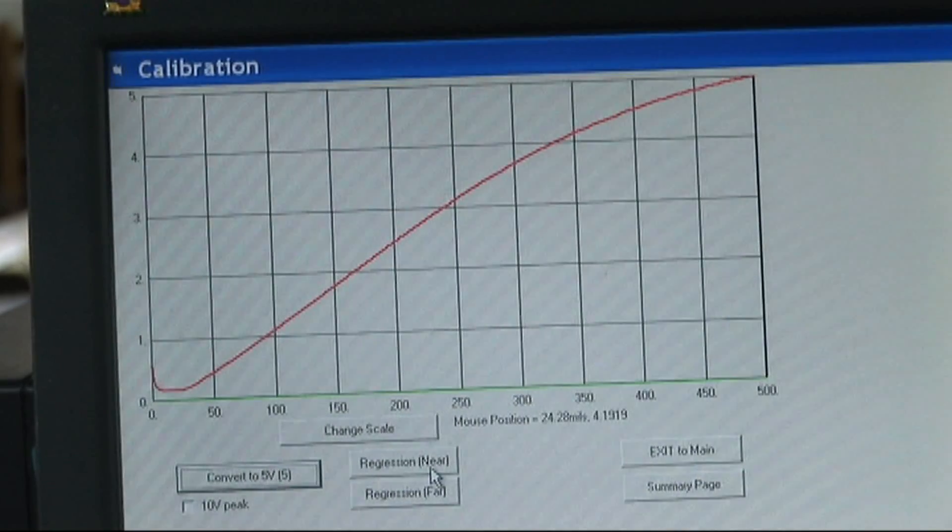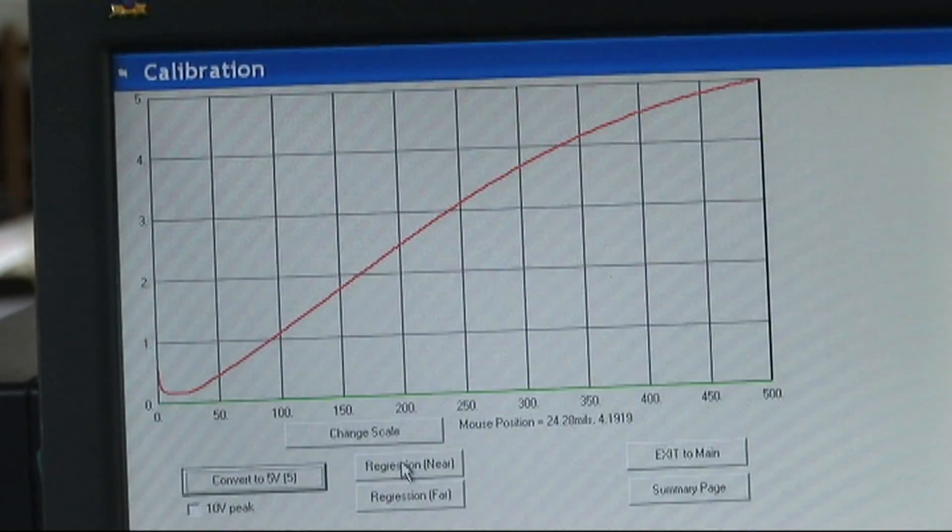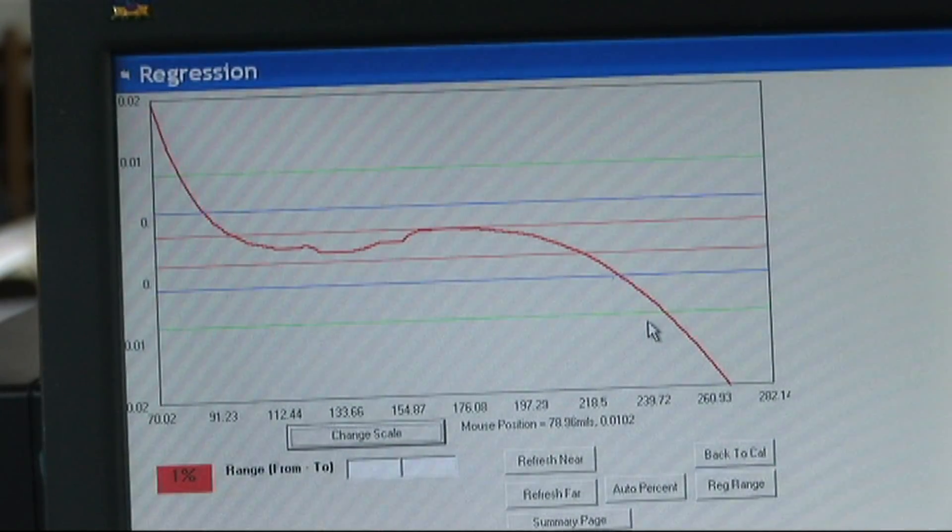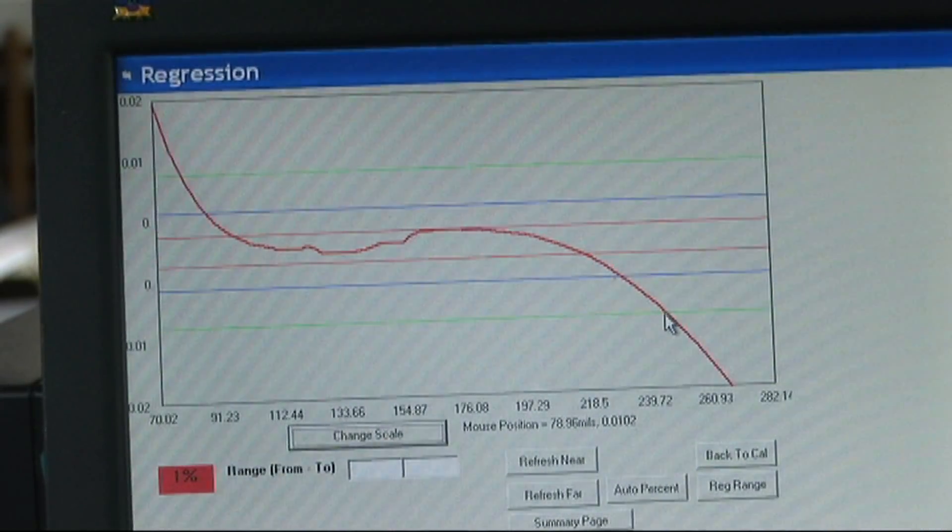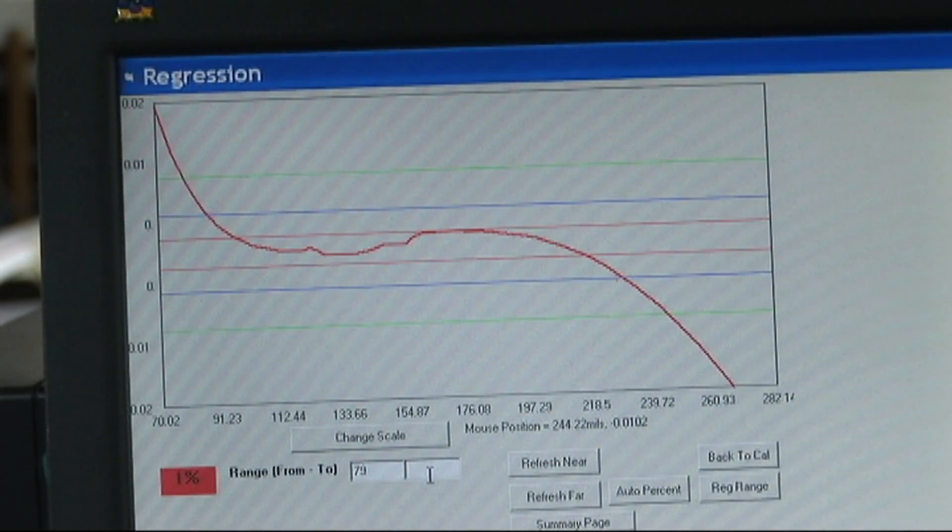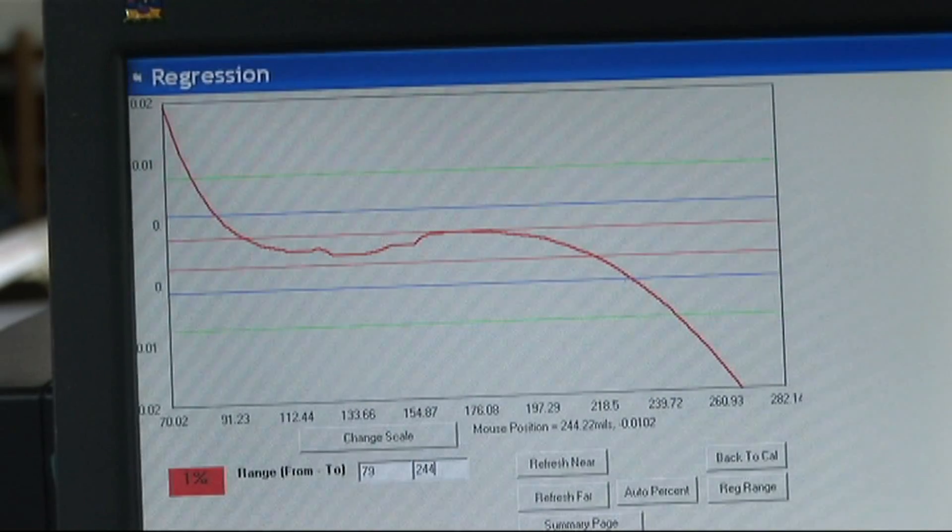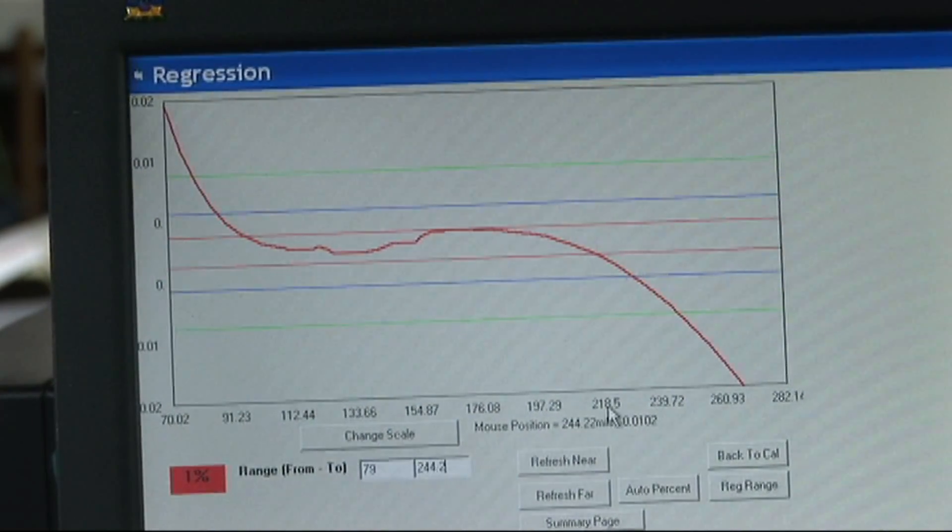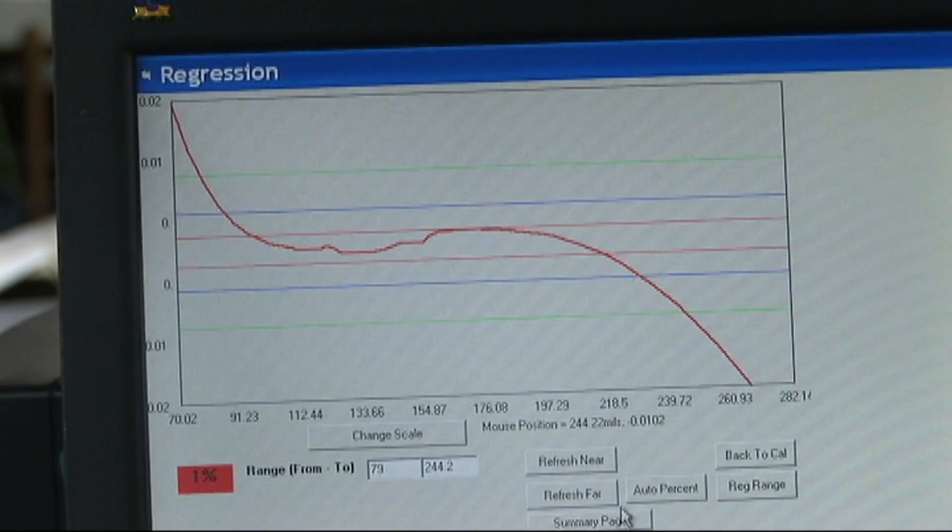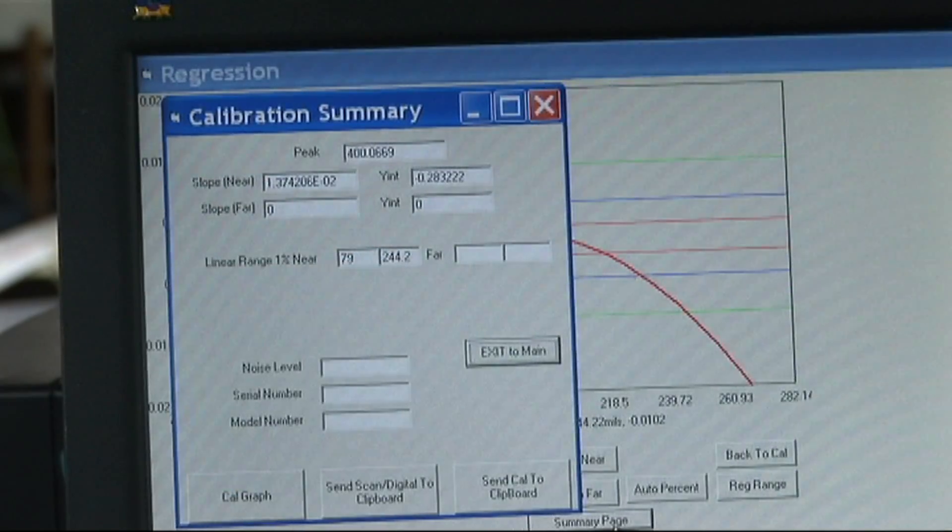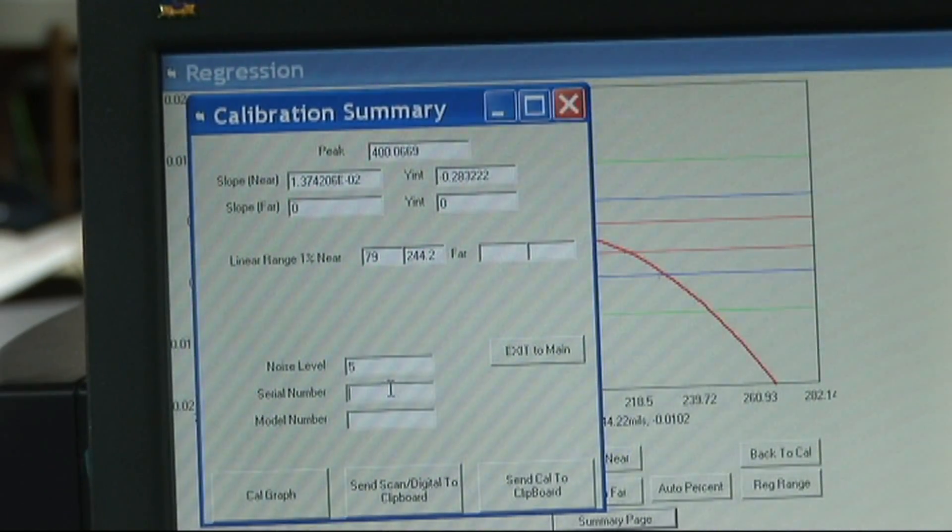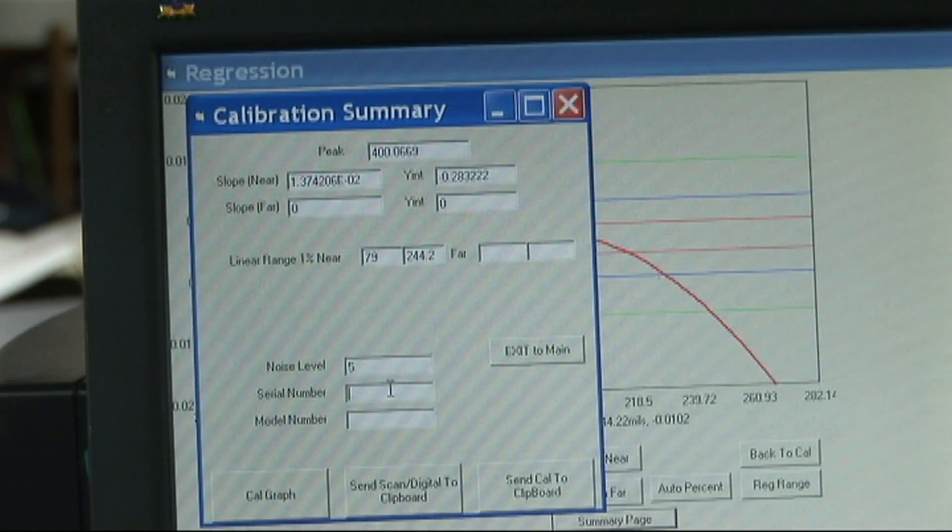But just to show you how we do the calculation, if I click on this regression button here, I could select these limits. I've got 78.96 or 79 mils on the low end, and we'll put 244.2 on the high end. Now what we've done here is defined the linear range. The green lines here show deviation from a straight line, plus or minus one percent. So now when I go to a summary page, we'll put a noise level of the sensor in, let's say five millivolts. This sensor, serial number is 2182.